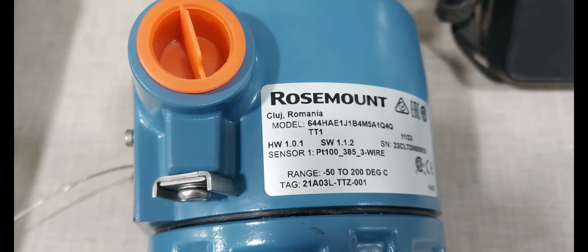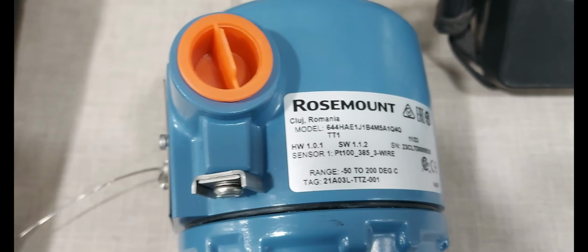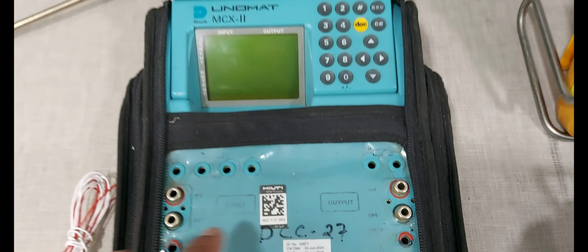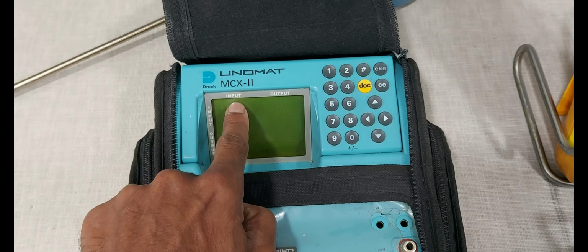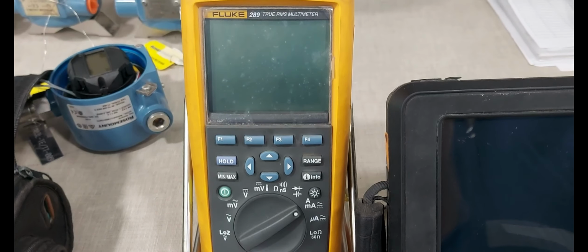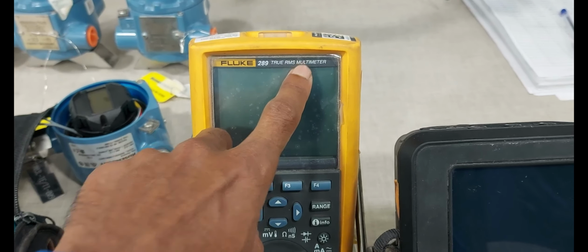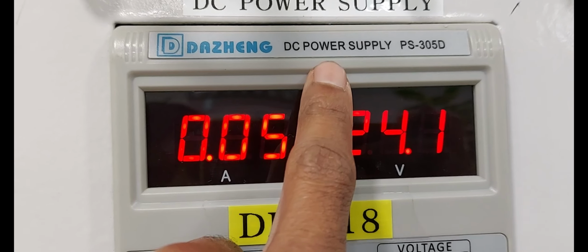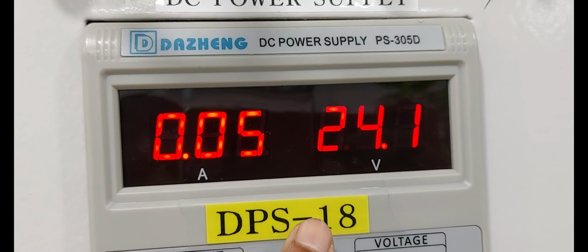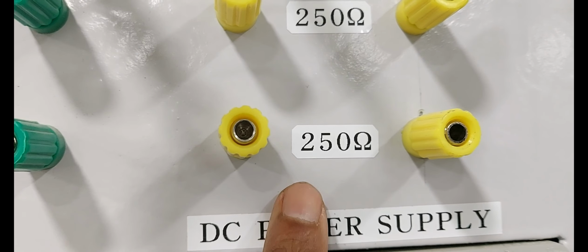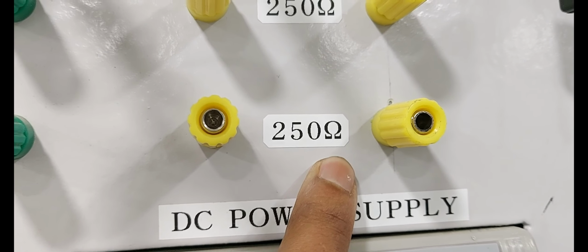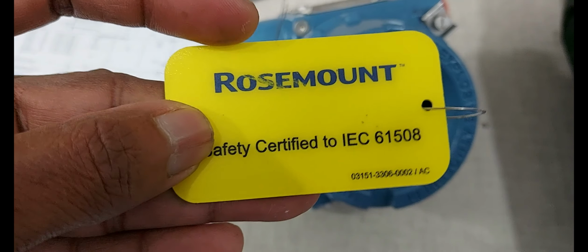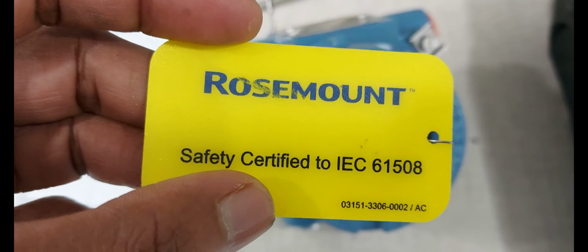The temperature transmitter calibration minimum required equipment: one multifunction calibrator, reference multimeter, one communicator for configuration purposes, DC power supply 24 volt, load resistance 250 ohms. This temperature transmitter is a SIL certified, safety certified transmitter.